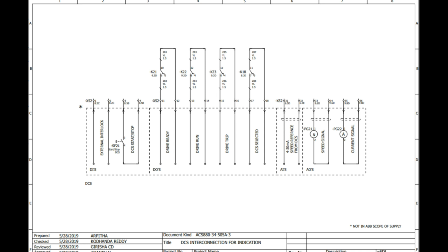Next we'll come to another slot, that is X52. This is for DCS, and the first channel and the second channel are for interlock. If required we will select it, if not we can skip it. Third and fourth are for the start button. This signal will come directly from the control; if it is running, okay, if not it will be no. Next, the digital outputs, the dotted middle one. So X52 channel numbers 11 and 12 are used for drive ready, K21. Similarly for drive running, K22 has to get NC, and similarly K23 has to get NC for drive trip. These are all DOs to DCS, digital outputs.